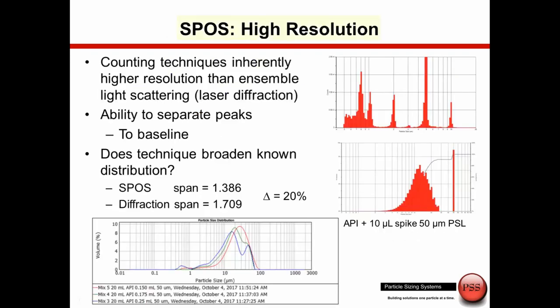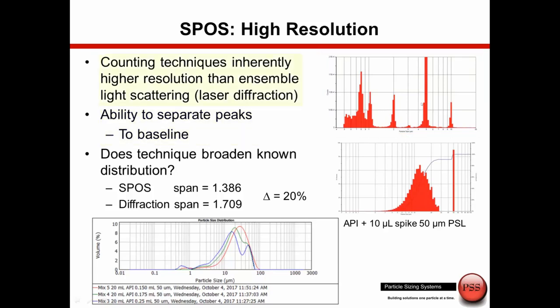Single Particle Optical Sizing is a very high resolution technique, and resolution can be defined several ways. One way is the ability to have many peaks and resolve them to baseline. Mixing five different latex standards, we can accurately identify where the peaks are, the width of the peaks, and what happens to the size distribution in between. Since we look at particles one at a time and build the distribution one particle at a time, it's much higher resolution than ensemble light scattering techniques such as laser diffraction.